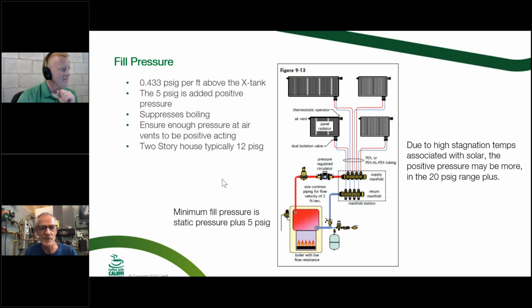So as I just showed on the previous slide, we want to ask, what is our minimum pressure that I pre-charge my tank to? Well, you need to know what the pressure of your system has to be to get 5 pounds of pressure at the highest point in your system. We always want 5 pounds positive pressure at the top of the system. So if I do have an air vent, or in this case just manual bleeders, when I open that, I'd like to have some pressure there to push the air out.